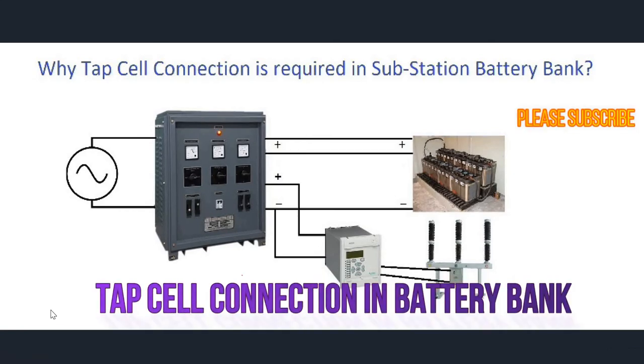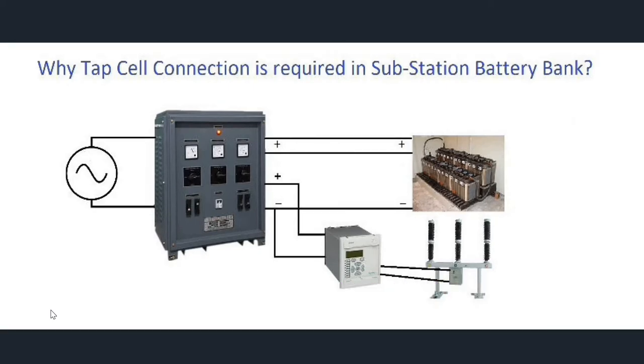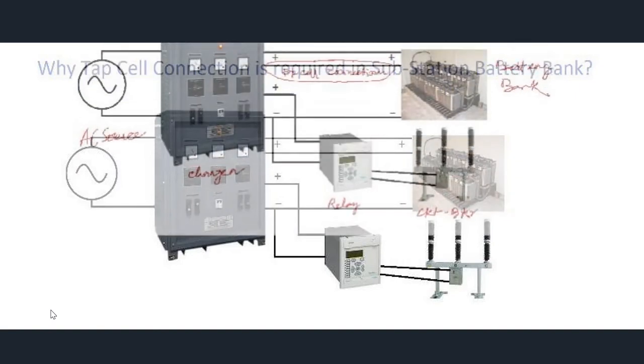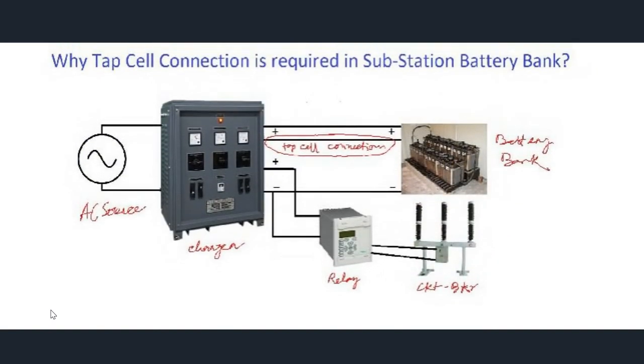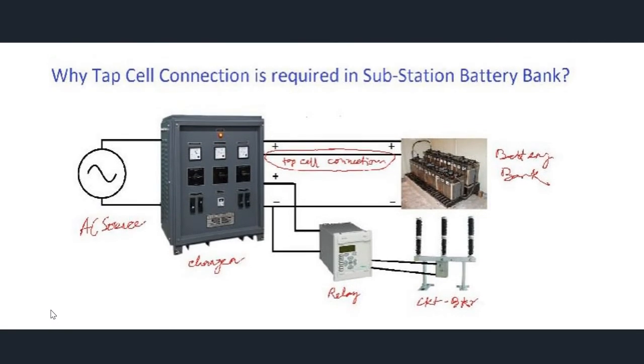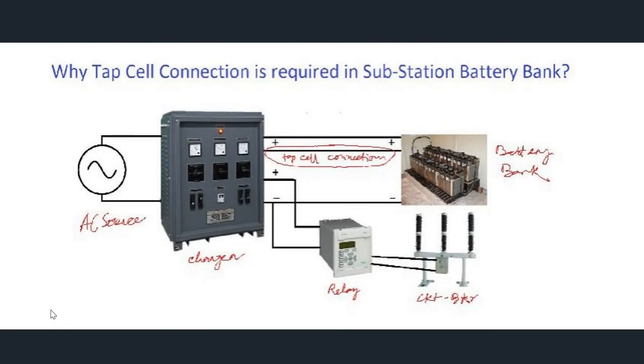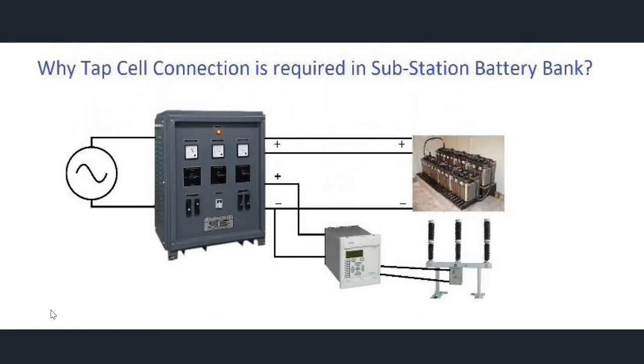Hi friends, today I'm going to discuss about why tap cell connection is required in substation battery banks. This is not too much required for students, but the people who are engaged in substations and power stations will require it the most. To start with, why is a battery bank required in a substation? Battery banks are required for the control of operating equipment like relays, circuit breakers, isolators, and many more.